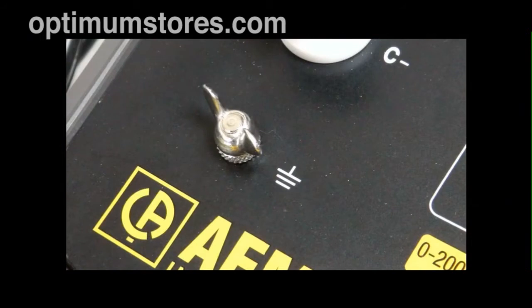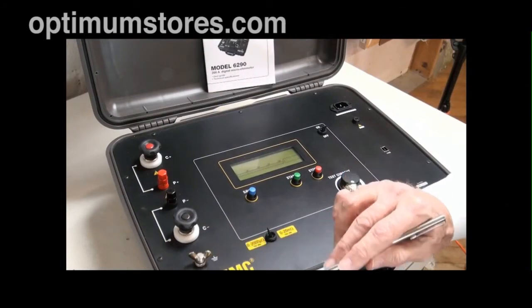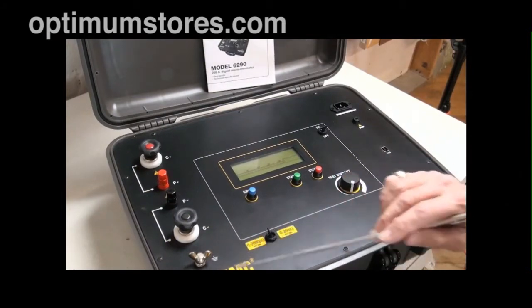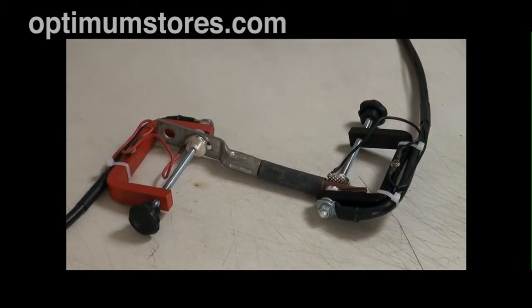And because in certain conditions in substations where you might have high induced voltages, you are allowed to ground out your test specimen. So that's an additional feature. For example, here would be a test we would conduct. We want to test the crimp at this point around the conductor wire. We would travel back to an area where we could access the conductor wire itself and go to the end of the lug itself. And now in this case we're going to pass current through the positive, out and return through the negative, and we're going to read across the device the potential, and that will tell us what the resistance is. We will calculate it at this point of the crimp.